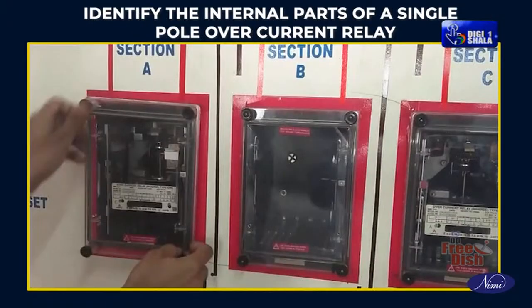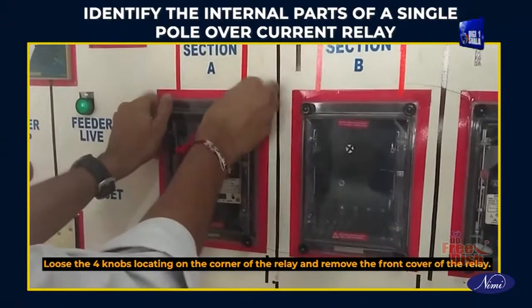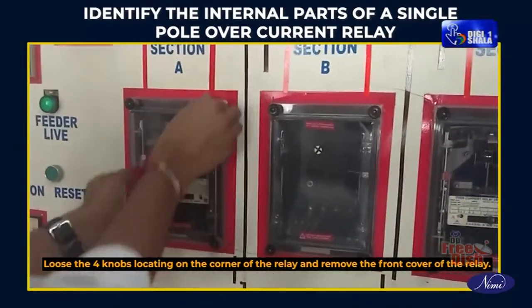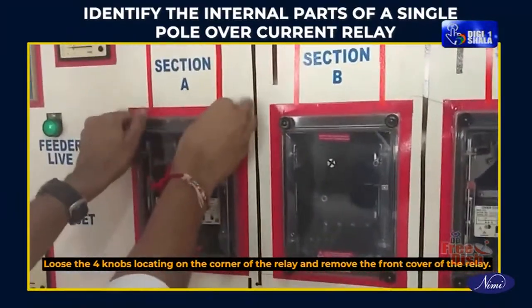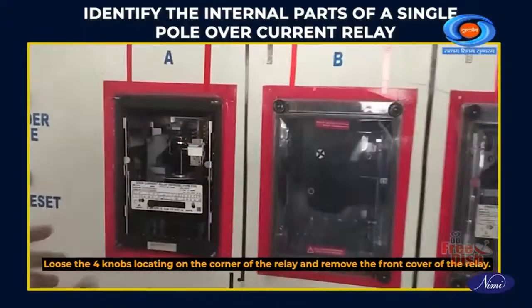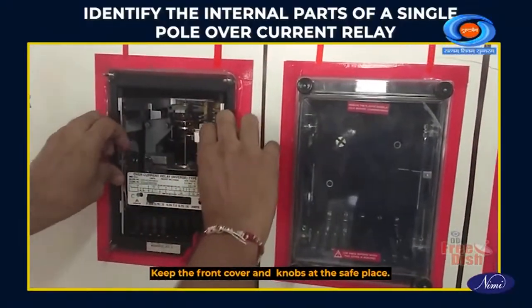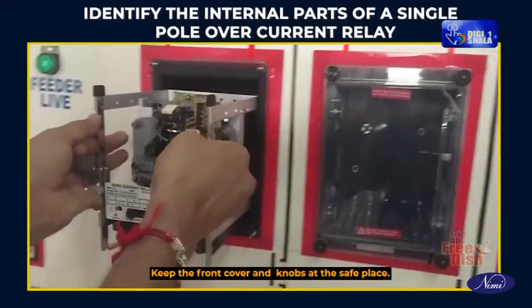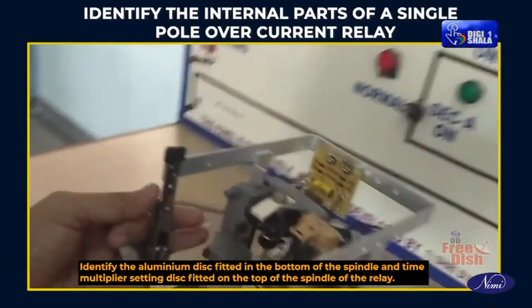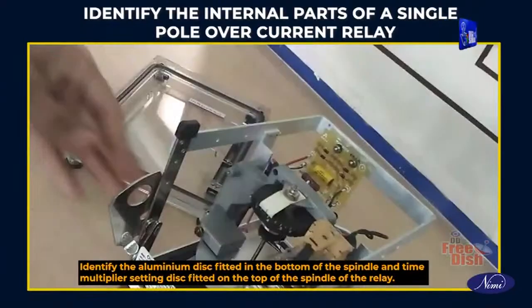Will it trip? Identify the internal parts of a single pole overcurrent relay. Loosen the 4 knobs located on the corner of the relay and remove the front cover of the relay. Keep the front cover and knobs in a safe place. Identify the aluminium disc fitted at the bottom of the spindle and the time multiplier setting disc fitted on the top of the spindle of the relay.